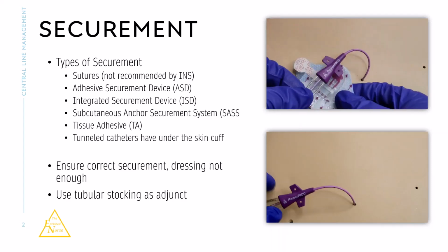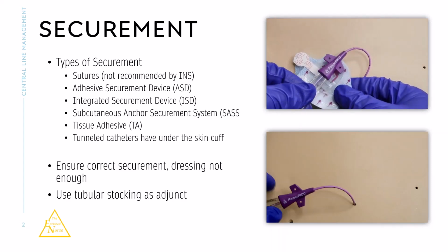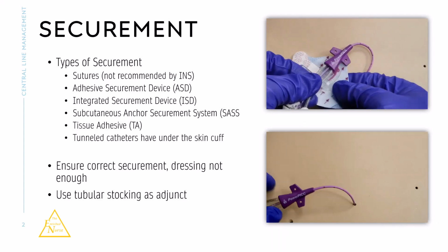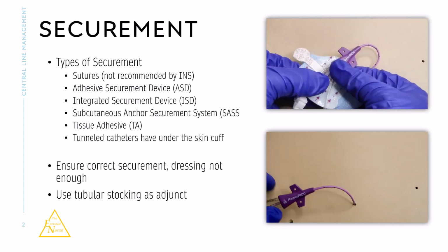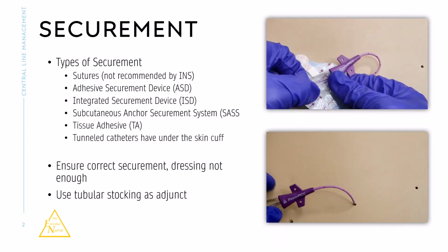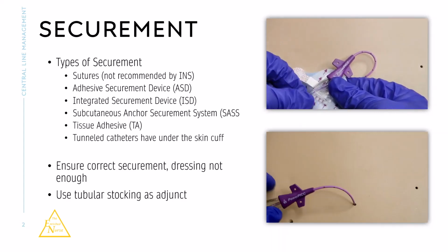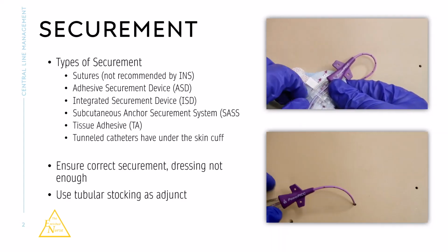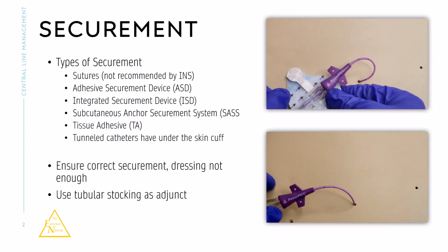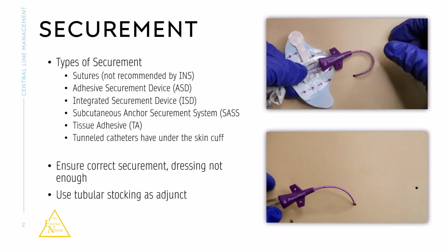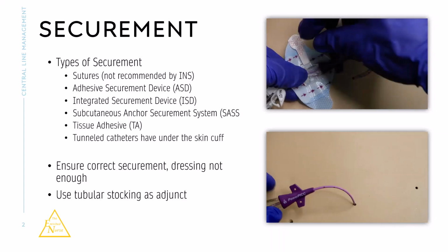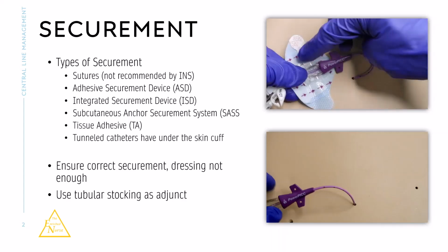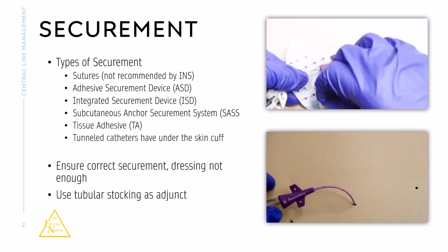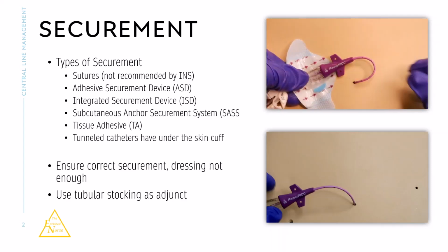So in that top one, you want to make sure that you follow the picture. So it actually goes above the hub. If you try to put those butterfly wings where that hook is, you're not going to be able to secure that catheter. With this hook type, you slide those little catheter pigtails underneath the hook, and then there's a tape strap that you can pull across. When applying these, you want to be really careful that you don't accidentally dislodge the catheter.